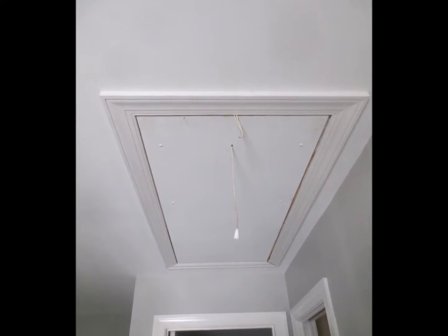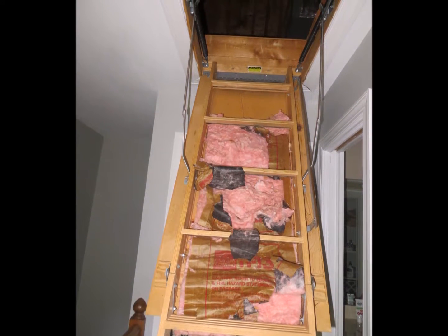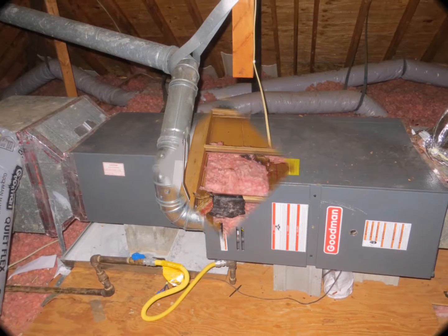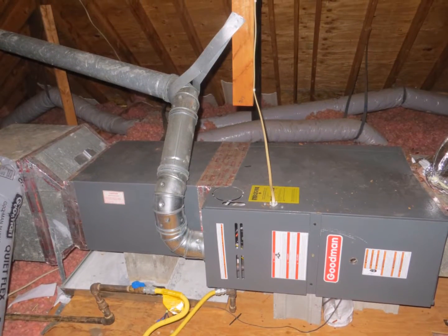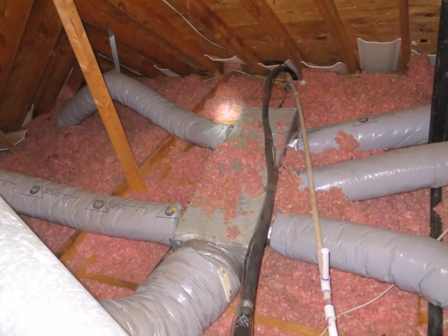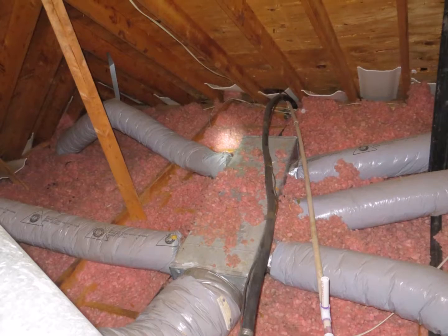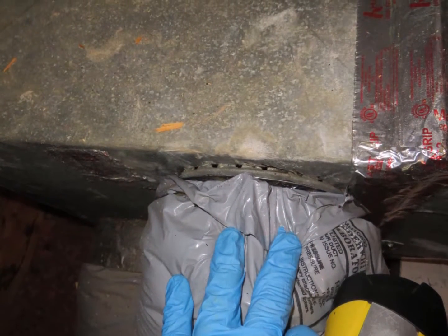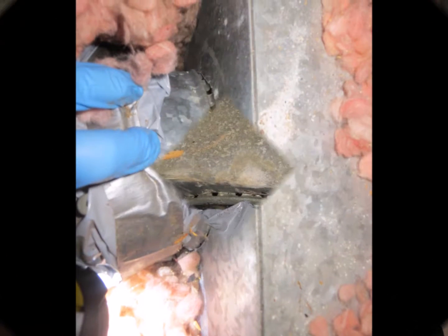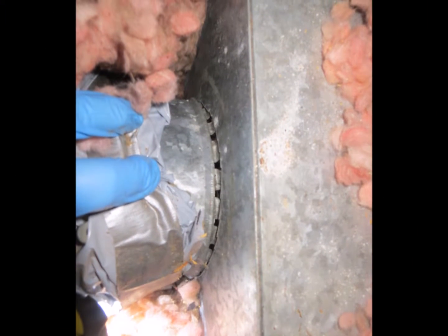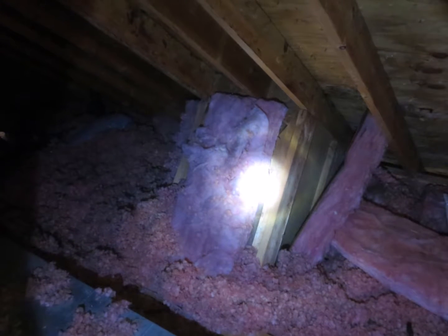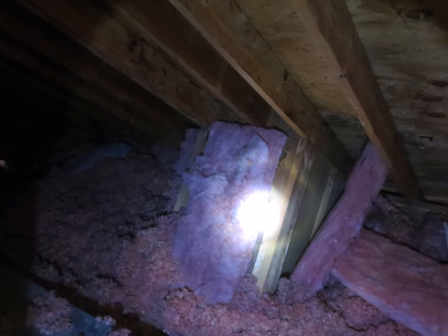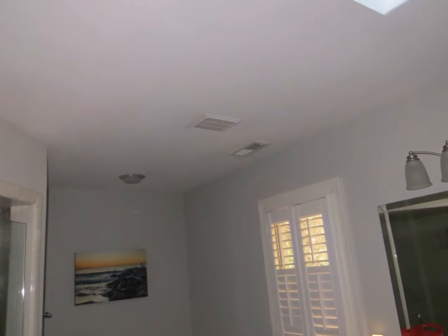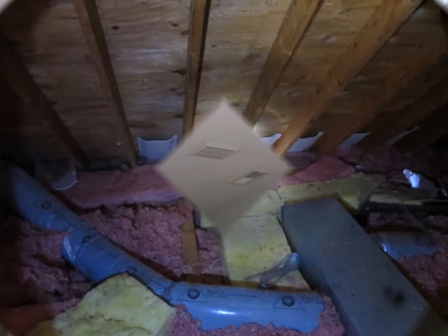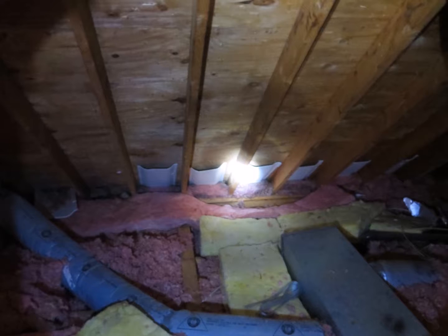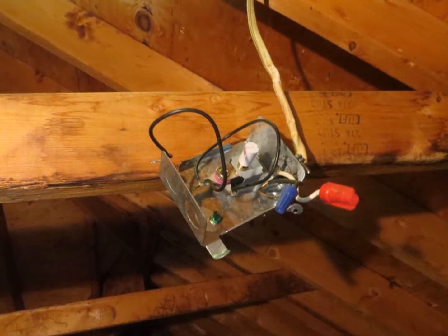The pull-down ladder for the attic is not properly insulated. This is causing a significant heat load on the hallway during the summer. The air handling unit is not effectively sealed or insulated to the degree that code minimum now suggests we have. The air ducts are not sealed, so all of these leaks are allowing conditioned air to slip into the attic. There are some areas where insulation is detached, such as the bathroom skylight. Also, the bathroom exhaust fan does not have an exhaust line that is evident in the attic. I'm afraid it's exhausting under the insulation.